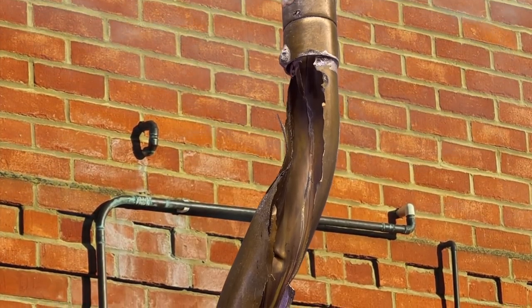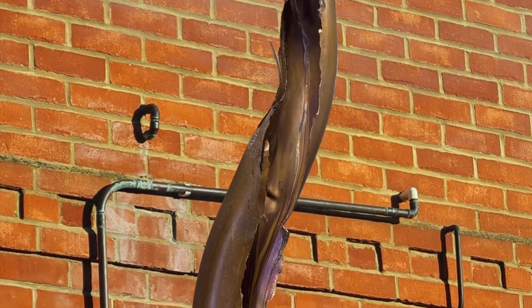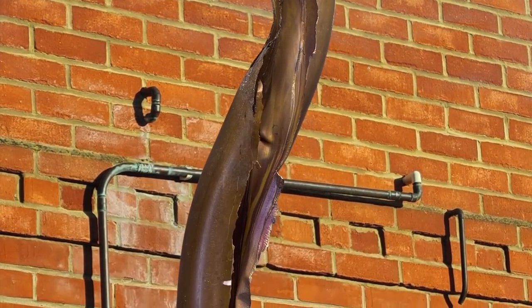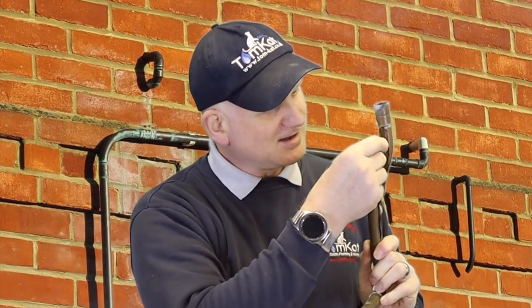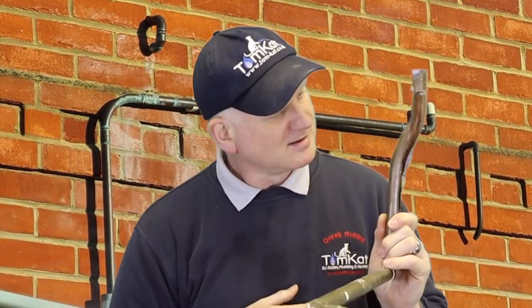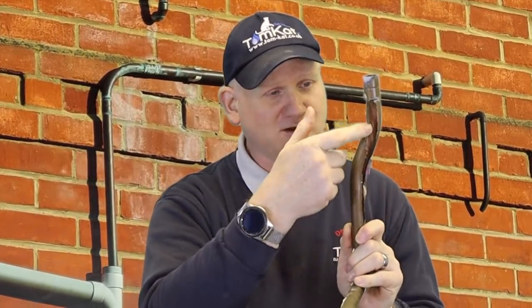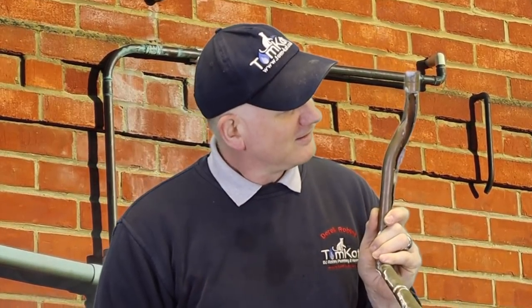Now, this is what happens to copper pipe when you use it as a condensate pipe. Can you see that? My very good friends Ben Green and Paul Cherry brought me this last week, and they gave me the inspiration to make this video because this is not very good, is it? So that's why we can't use copper, because it just corrodes it. And yes, guys, this was on a boiler condensate pipe. And why did the customer not notice that? Anyway, cheers Ben and Paul for bringing that in and giving me the inspiration to make this video.